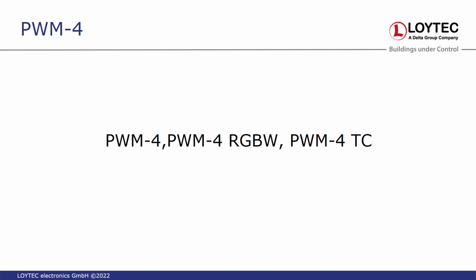It should be DT8, no? DT8, yes. DT8 is the color control for lamps in the DALI standard. So both the TC and RGBW versions will be seen as DT8 devices. Okay, perfect.